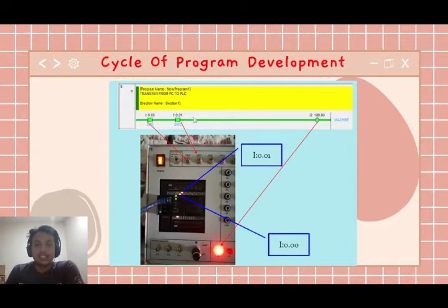We have reset the ladder diagram in the PC. Then we can use the panel of the PLC set by the PC. We can see the indicator of input 0.01 is lit up, and the indicator of switch I0.00 is off. Then the input also lights up. This is for switch 1. This is for switch 2. Then the indicator will turn on following the switch, and from the ladder diagram work online method, we can see the light is up, then the panel also will light up.